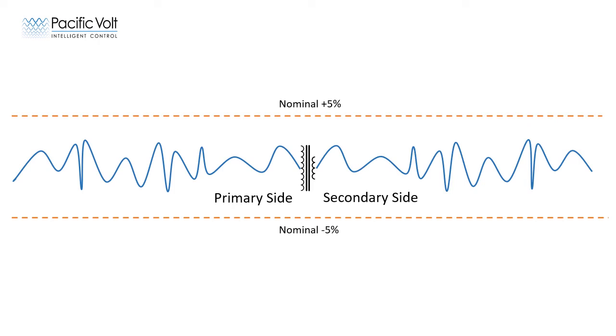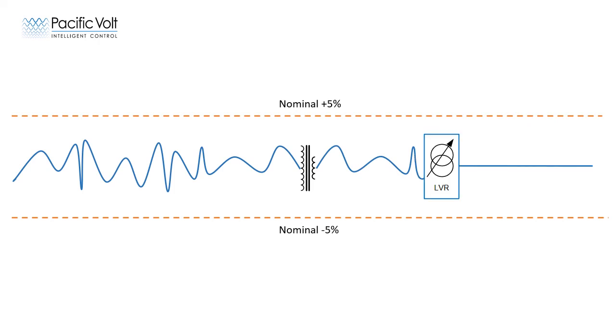It can be caused on the primary by a large industrial load, and since transformers are magnetically coupled, flicker on the primary is also transferred to the secondary voltage, where it can be mitigated by an LVR. The LVR compensates for the change in voltage 20 times every cycle, which is 72,000 times a minute. This subcycle response will effectively mitigate flicker on the low voltage circuit.